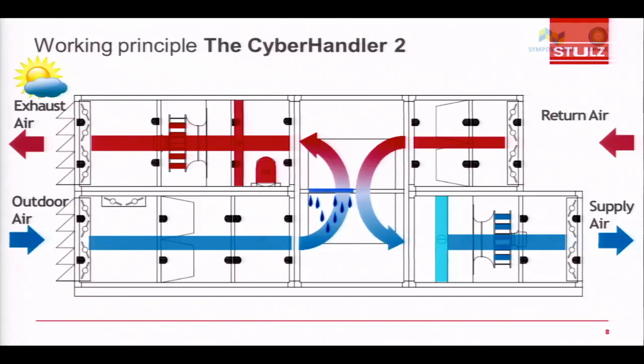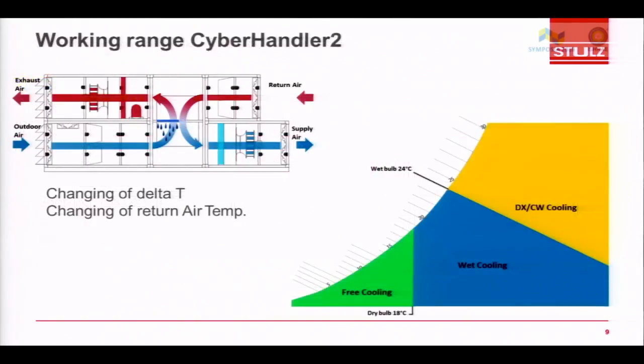But again, understand the air to air heat exchanger is indirect cooling. It is like a shell and tube condenser. No outside air is going to come in contact with data center air. Data center air, we call it 5 microns. So the filtration level of the data center inside air will be maintained, and outdoor air, which is polluted and has toxic gases and everything, will not come in contact with the data center.